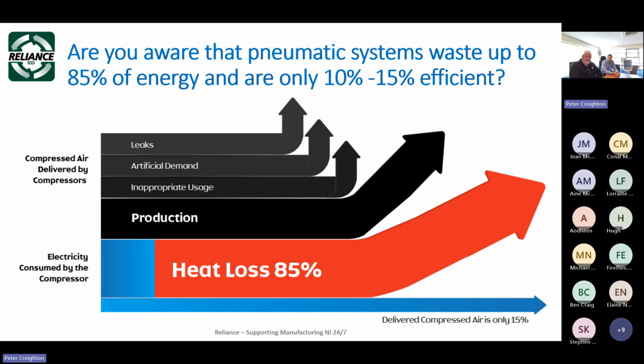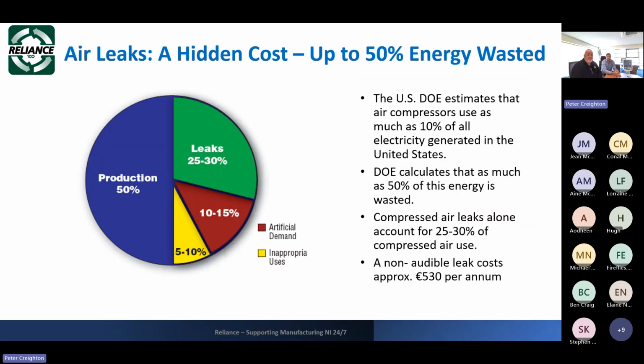What that means is that when you're generating your air, the cost of running your motor, by the time you get air out onto the production facility, you only get 15% of the value that was put in first day. That's frightening enough in itself, costs absolutely massive money. But then when it does go onto the facility, we find that you only get 50% of the 15%, due to leaks and inappropriate uses and artificial demands. Now, all of a sudden, that is 7.5% efficient. So if you're running a 200 kilowatt motor and it's costing you, just say, 10 cents an hour or 10 pence an hour, all of a sudden you're getting 7.5% back. It's a massive, massive draw on your consumption.